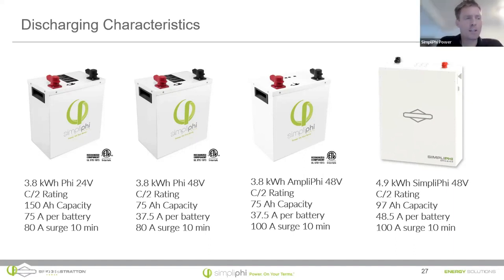It's a good question. And again, I think that the answer is unclear. If we saw a huge difference, I think we would probably advertise it. I think that 20% state of charge is not that low. And to my knowledge, we don't have numbers like 15,000 cycles if you only do a 50% depth of discharge. Because batteries are fairly expensive, right? Most people are wanting to get their value out of the battery by discharging and using that full capacity of the battery. I can tell you that there is a big difference between discharging to a 20% depth of discharge and discharging to a 10% depth of discharge.